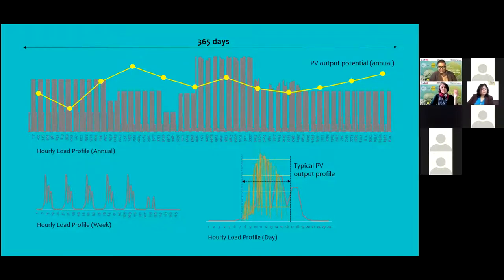And even though the building may achieve a net zero energy at the end of the year, there will be certain months, like say in the monsoons, where it is taking more from the grid than it is supplying back. And in some months it would be vice versa, there would be a surplus. So if we look at this onto the daily profile, it gets even more complex. In a real life scenario, we rarely see a smooth curve, especially in cases of cloudy days. The building's own load demand on the grid keeps going up and down, and it causes issues on the grid.